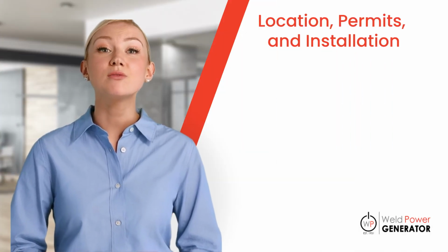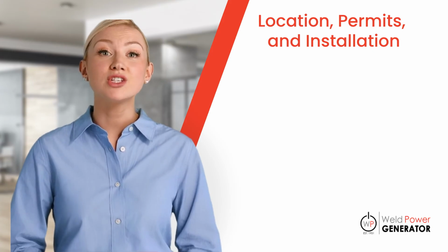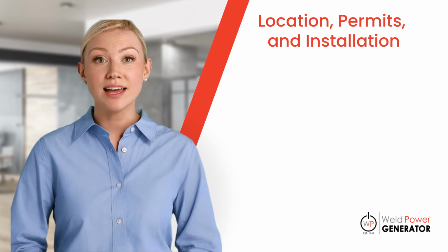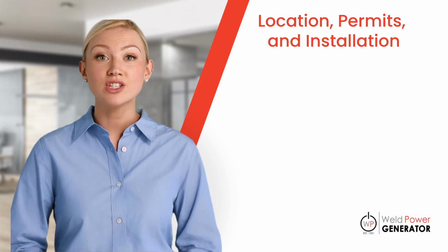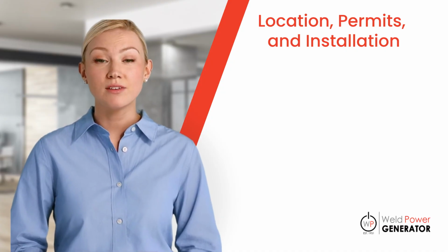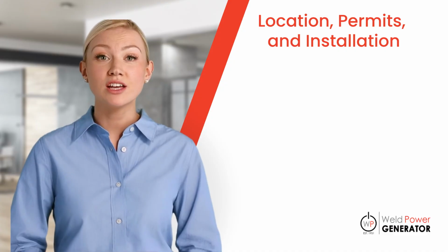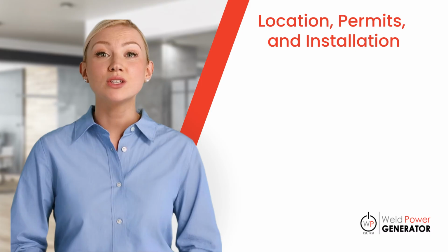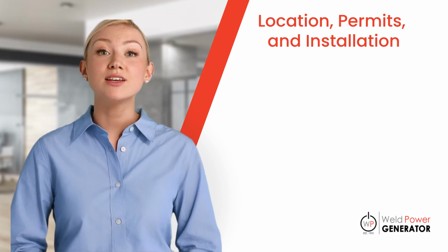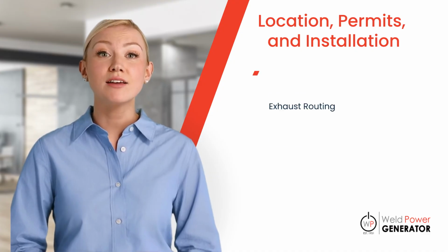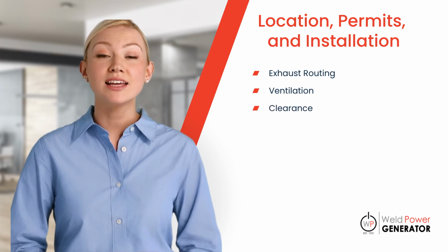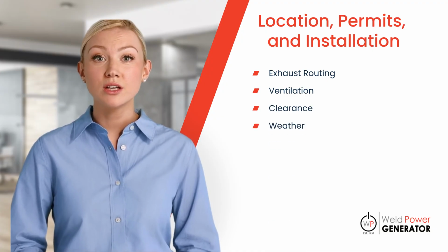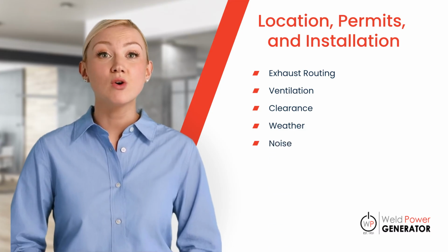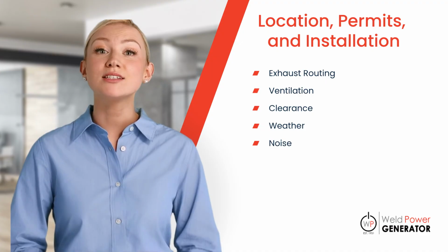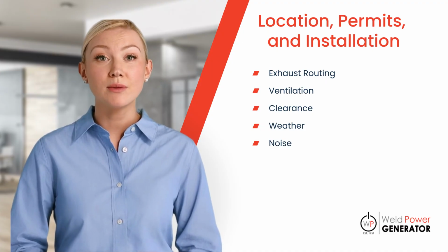Choosing the right location for your commercial generator installation is a critical step that directly affects safety, performance, and compliance. Depending on your facility's layout and operational needs, you may opt for an indoor installation, an outdoor pad-mounted unit, or a trailer-mounted generator for mobility. Each option comes with its own set of pros and cons. For example, indoor installations demand strict attention to exhaust routing, ventilation, and clearance to prevent overheating and ensure proper airflow. Outdoor units must be housed in weatherproof, sound-attenuated enclosures to protect against the elements and reduce noise levels in accordance with local noise ordinances. Regardless of the setup, proper spacing around the generator is essential for maintenance access and fire safety.